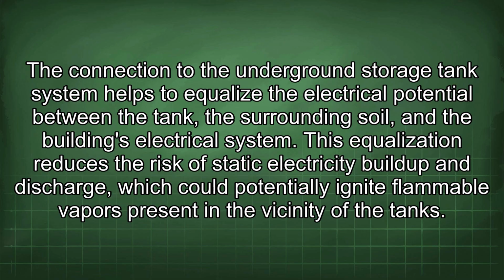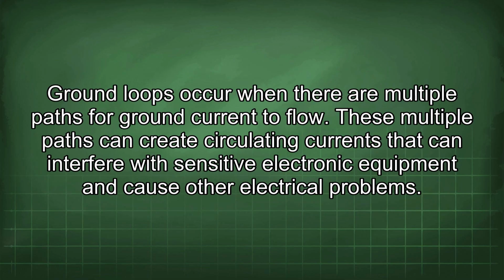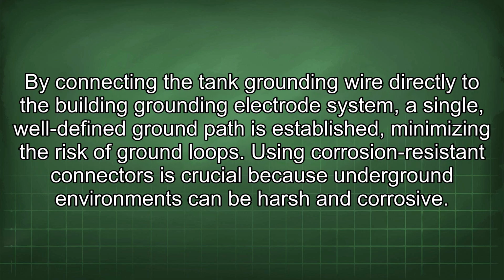Ground loops occur when there are multiple paths for ground current to flow. These multiple paths can create circulating currents that can interfere with sensitive electronic equipment and cause other electrical problems. By connecting the tank grounding wire directly to the building grounding electrode system, a single, well-defined ground path is established, minimizing the risk of ground loops.